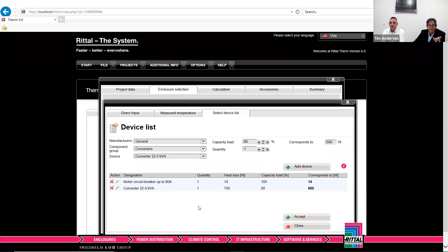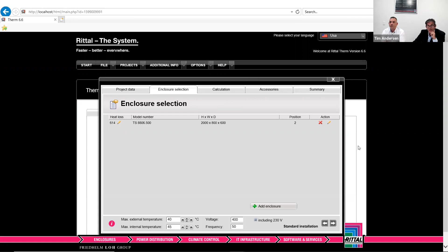Now, going back to this, I said the maximum external temperature could only be 40 degrees, so it might be somewhere in Tasmania or Victoria, even though they do get odd hot days. And then you've got the maximum internal temperature of 45. I'm bringing you back to that because it's going to affect our calculation. Now, we're going to hit the calculation button, and once this screen's presented, you've got all this wonderful, exciting information. You'll see that starting at the top, the software's calculated the surface area. Based on its K factor, it's also determined, if you don't put any cooling on this, it can dissipate about 140 watts of heat through its surface area. But it's also giving you a nice heat load figure of 474 watts, okay?